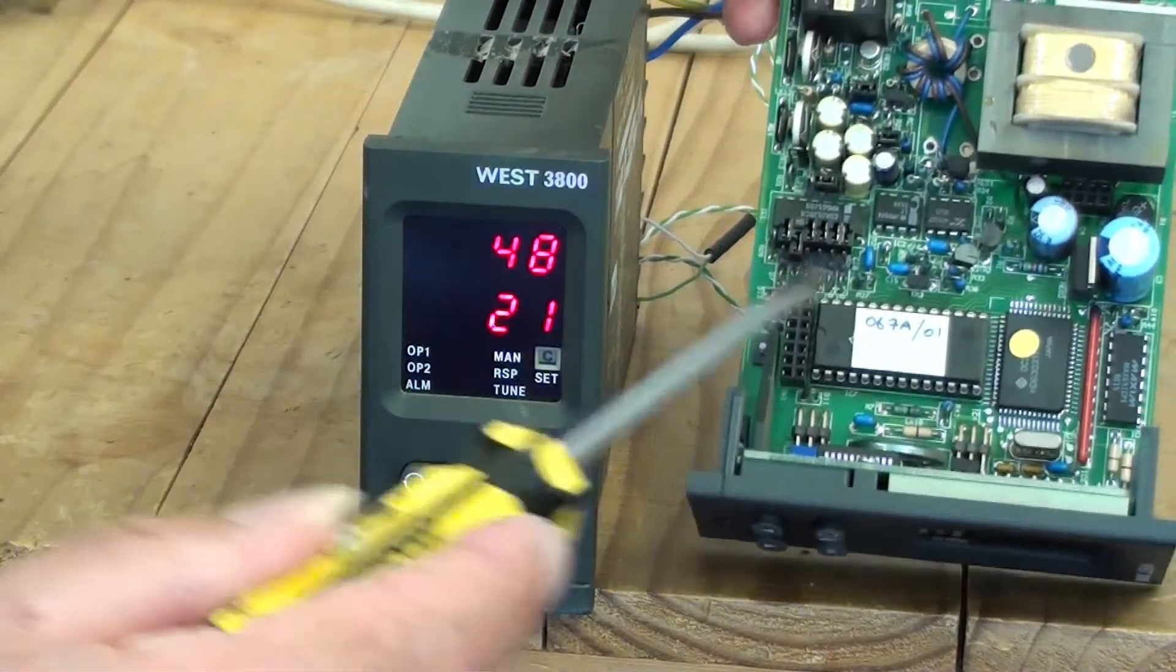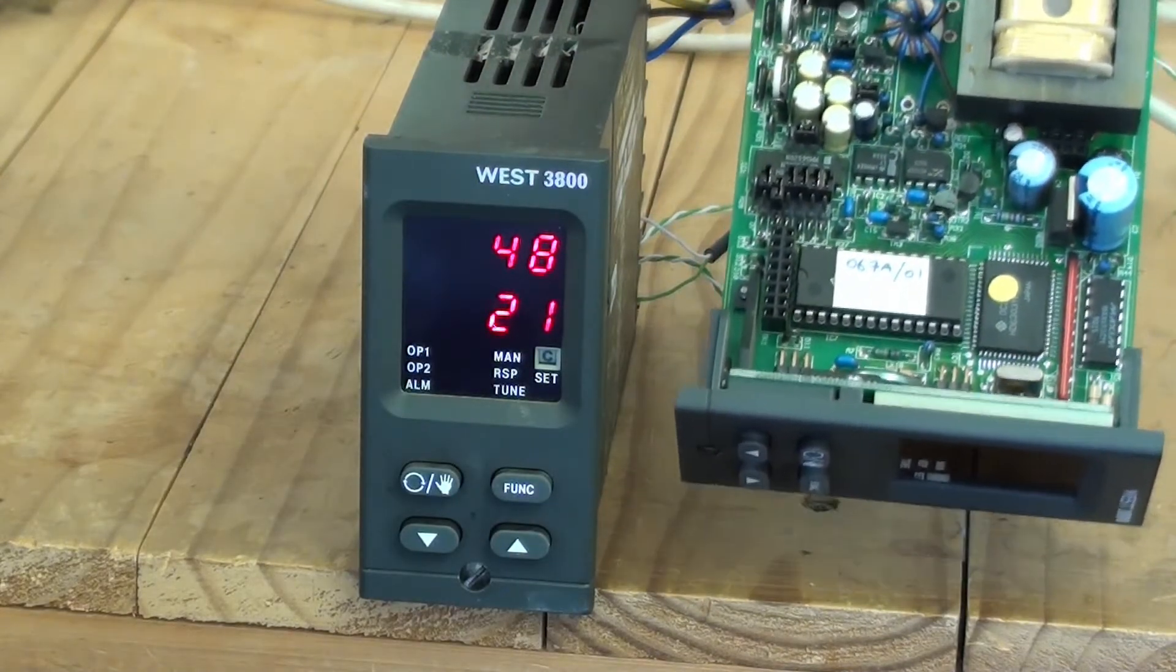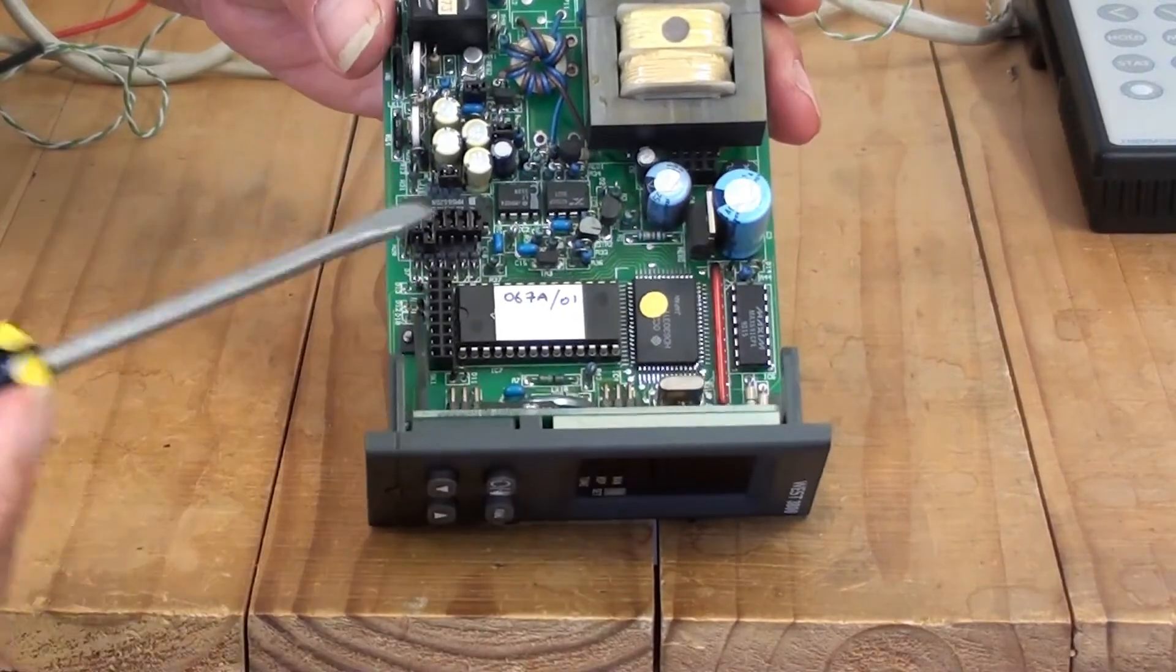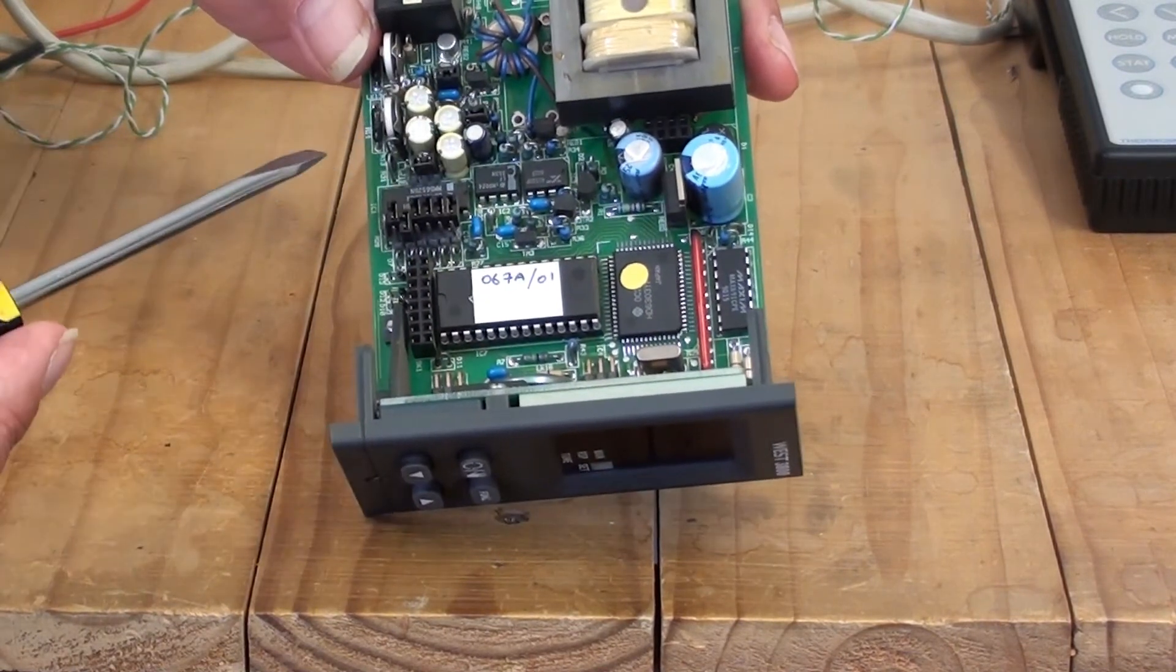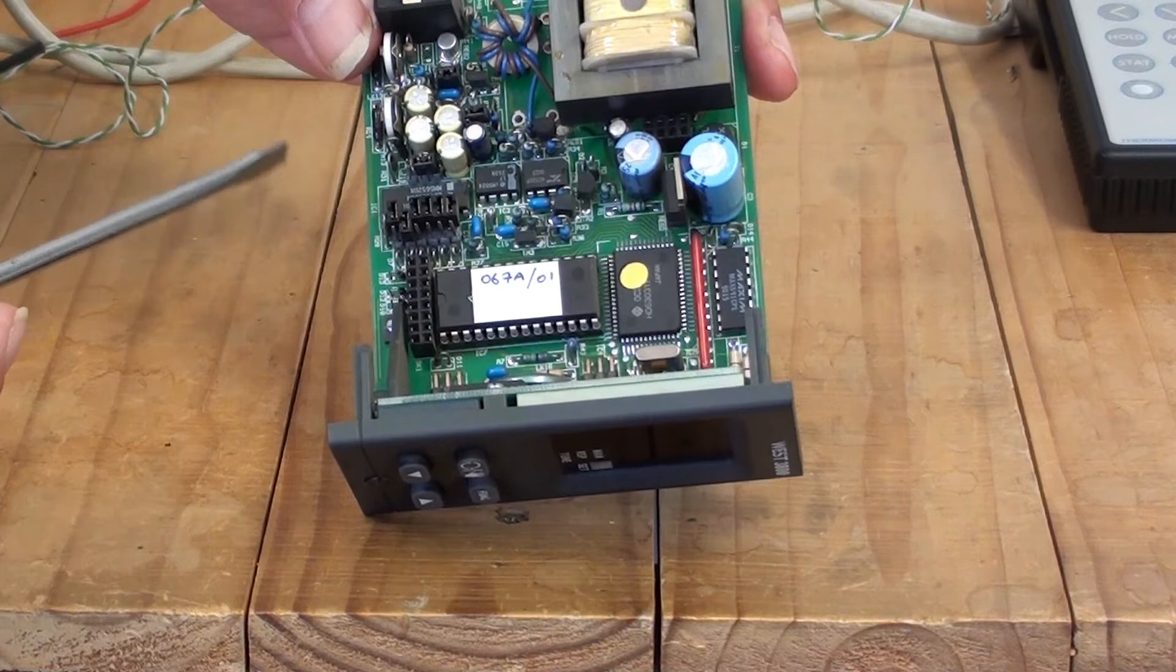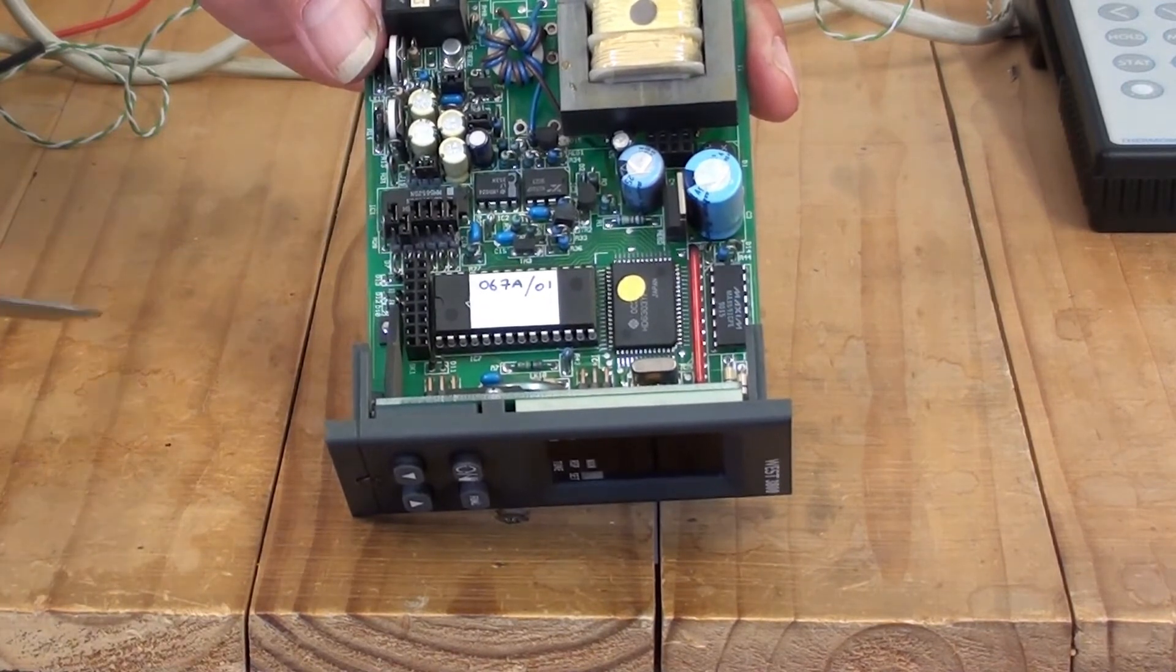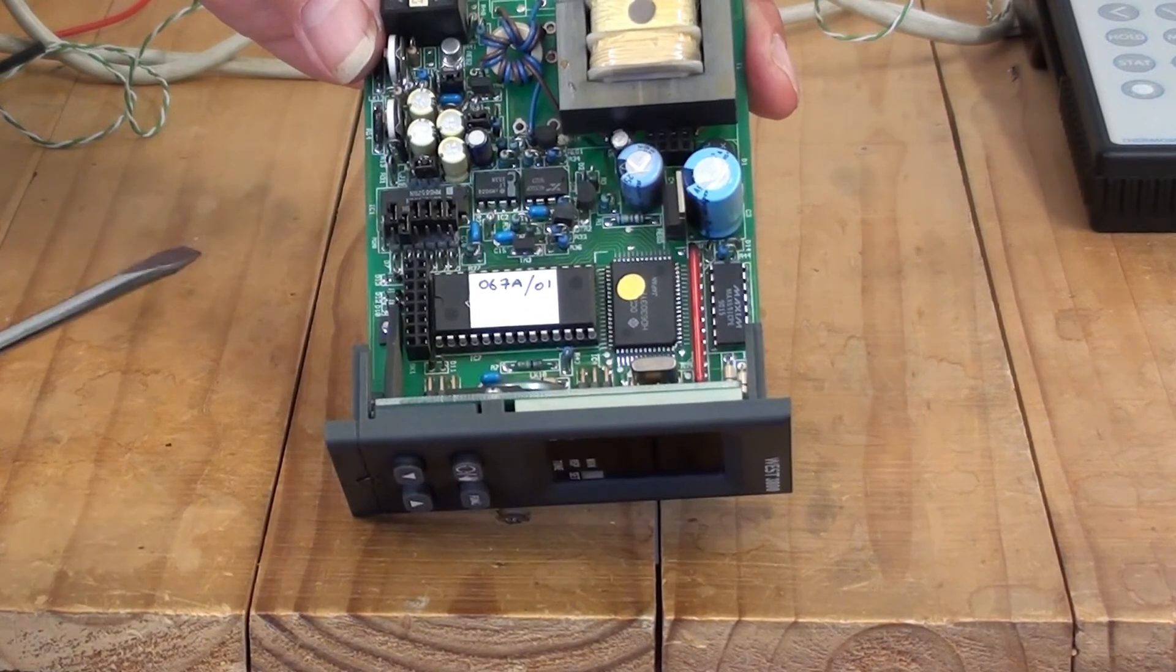Now we'll look at the link jumpers here which is how the controller would have been configured in the factory for the type of input signal. Here are the link jumpers here, here and here, and it's the selection of these link jumpers - whether the link is made or if they're parked - that would determine the configuration of the controller for different types of input, for thermocouple input and what type of thermocouple it would be and the range, or if it's RTD and so on. That was done by selection of these link jumpers.